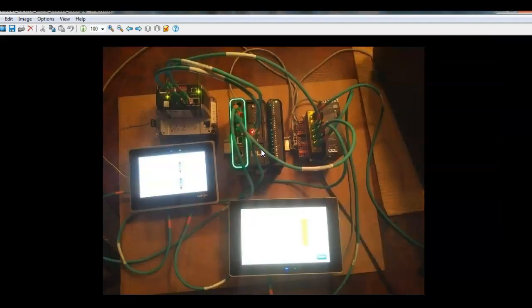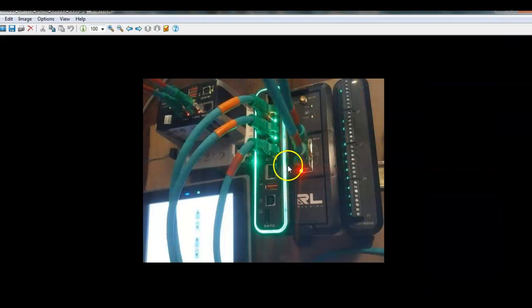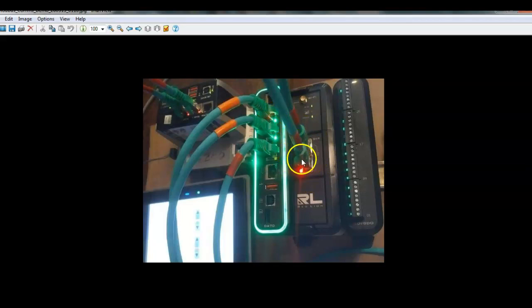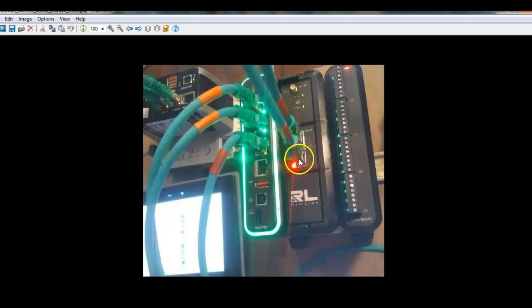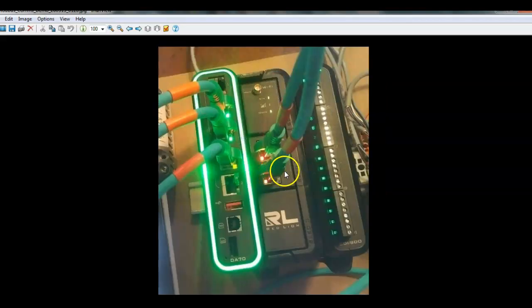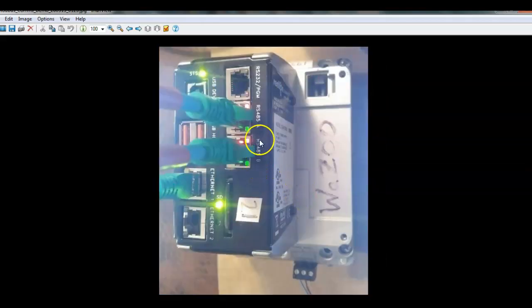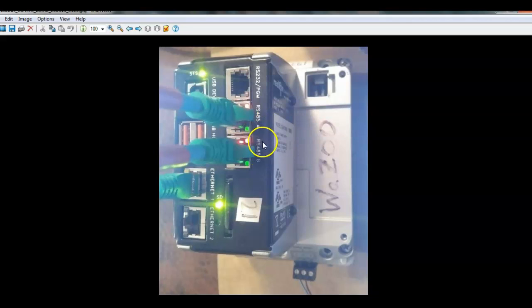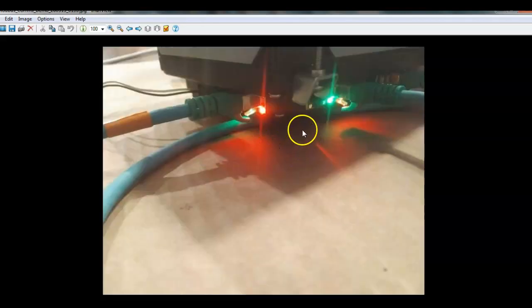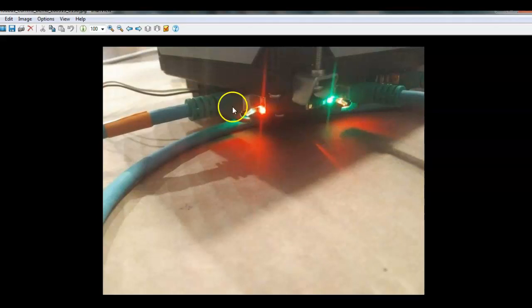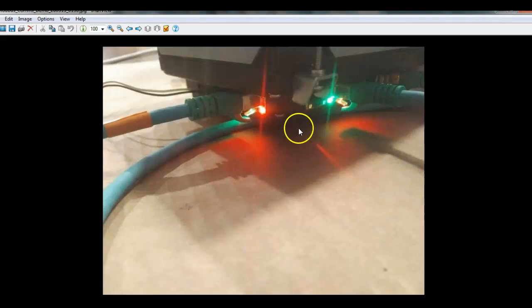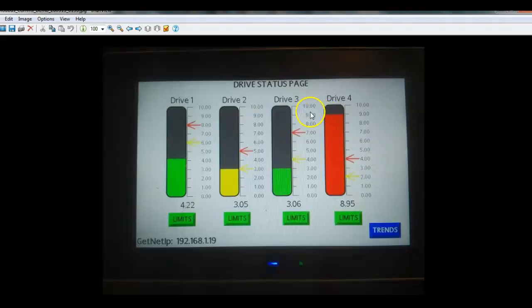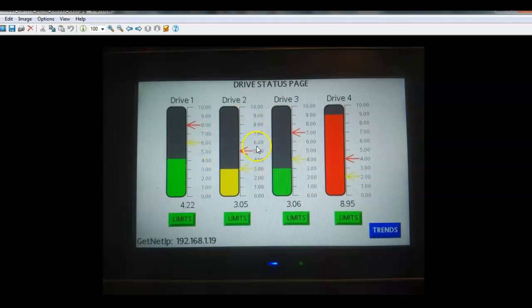There is an RS-485 port here and another RS-485 port here. Both of these cables are plugging into the 7-inch HMI Modbus 485 slave ports. That's going to be drives 101 and 102. And then on the same edge there's a sled with a two RS-485 port sled. One of these cables goes to this connector and the other port goes to this RS-485 COM. Then this connector goes over to the Ethernet switch for Modbus TCP.